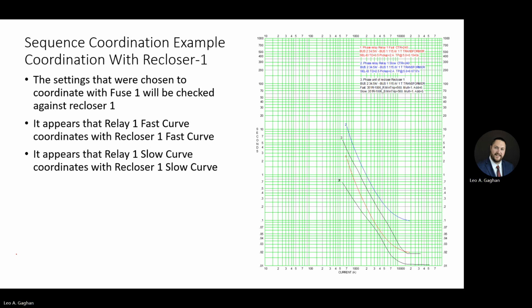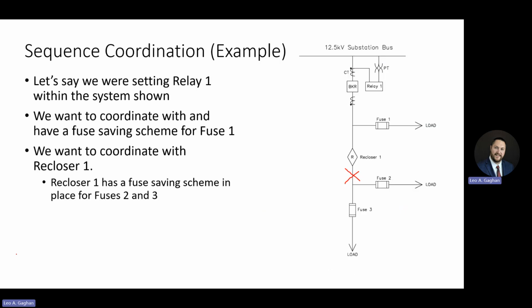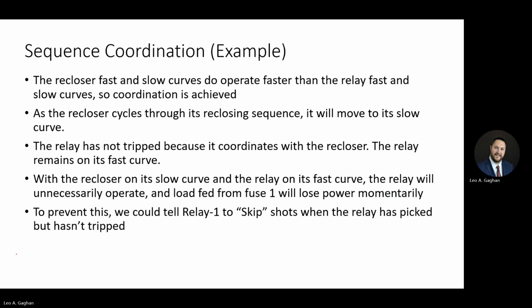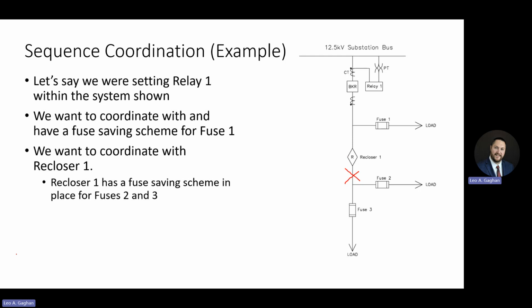Now, if that happens, if the relay stays on its fast curve, curve 1, and the recloser moves to its slow curve, which is curve 3, then the relay is actually going to trip faster than the recloser, and the load off of fuse 1 are going to lose power when they didn't have to, and it could have been prevented. So the way that we address that is we are going to have something called a skip shot. When the skip shot occurs, we're going to set up the relay to skip a shot whenever the relay picks up, rather than when there's a reclose initiate based on a trip.